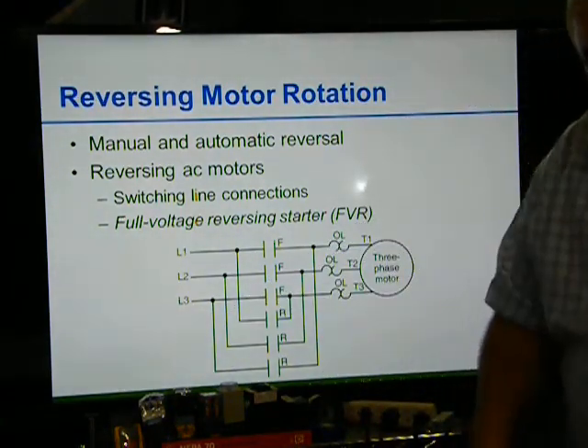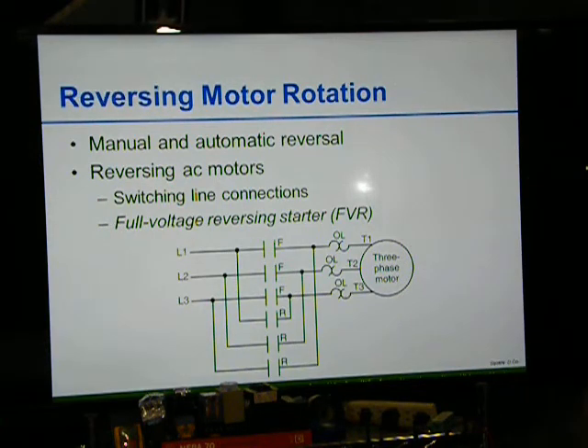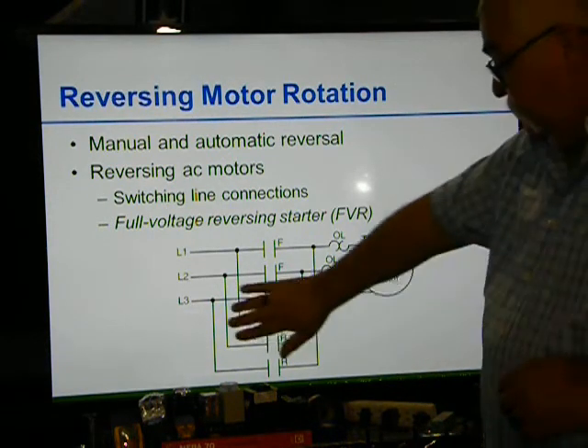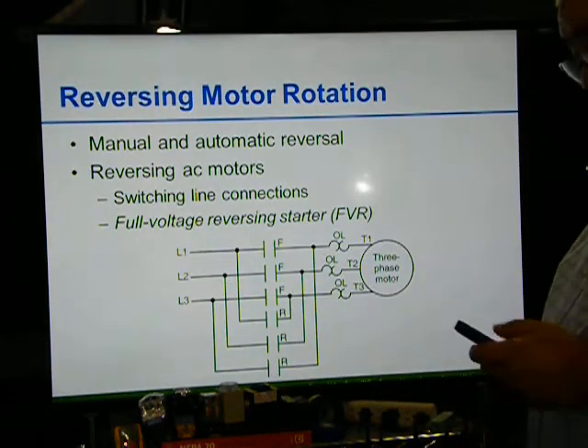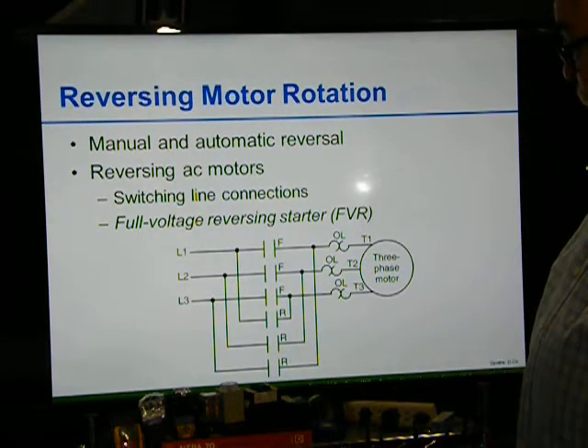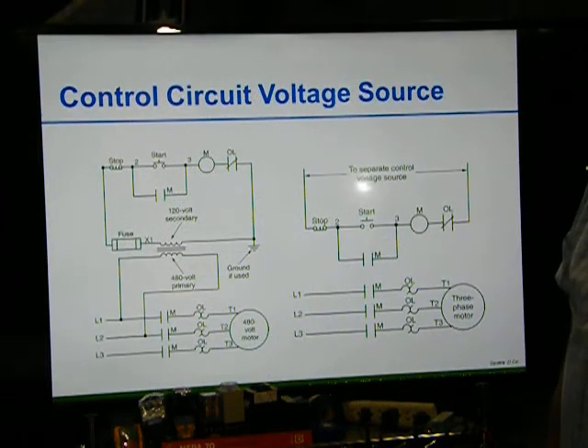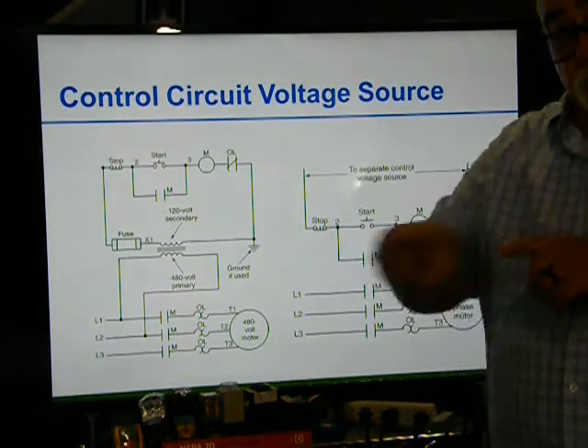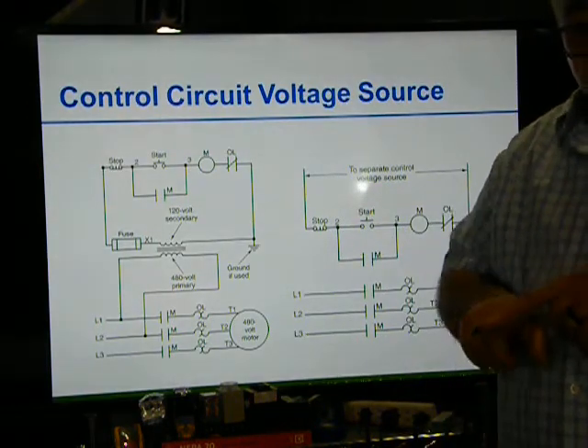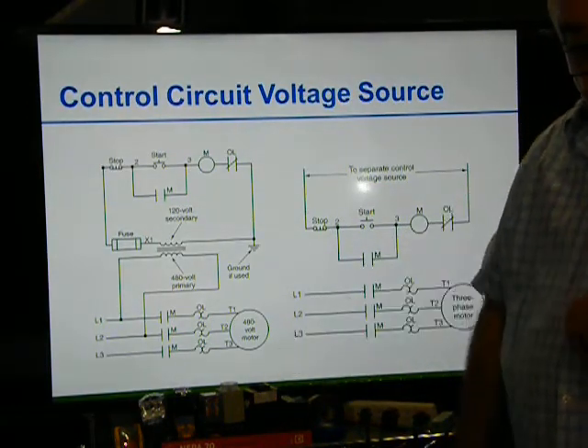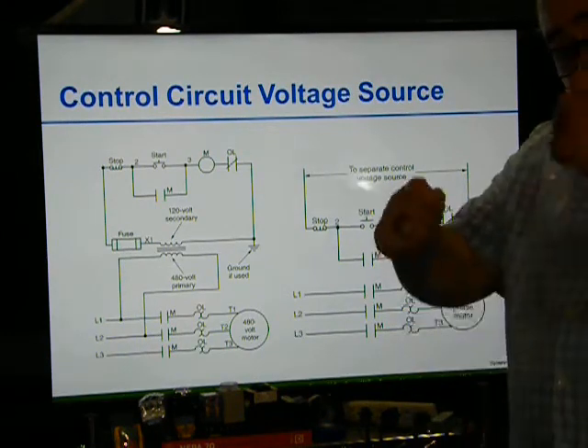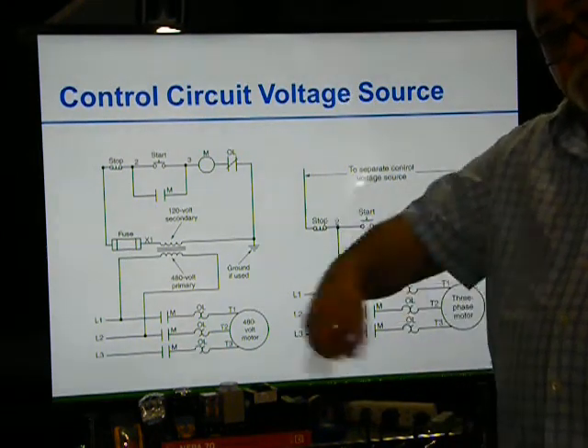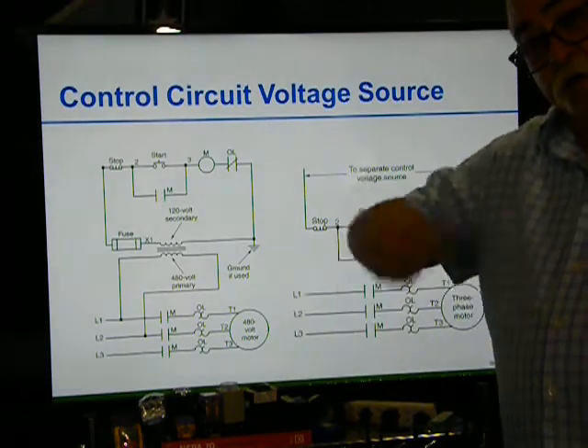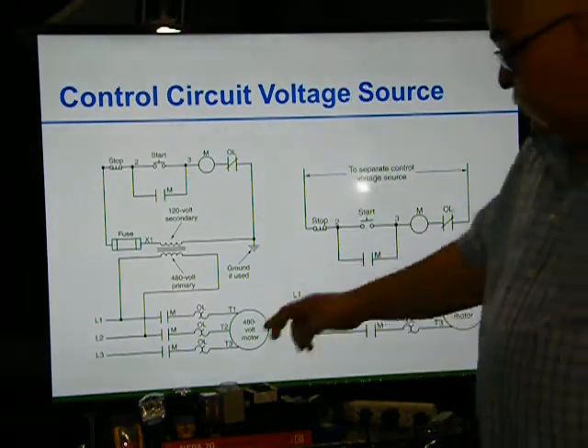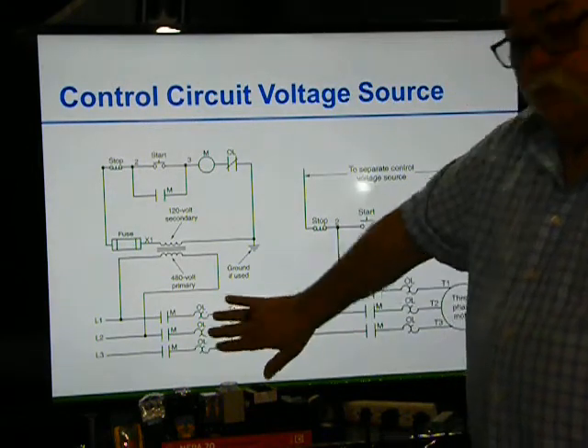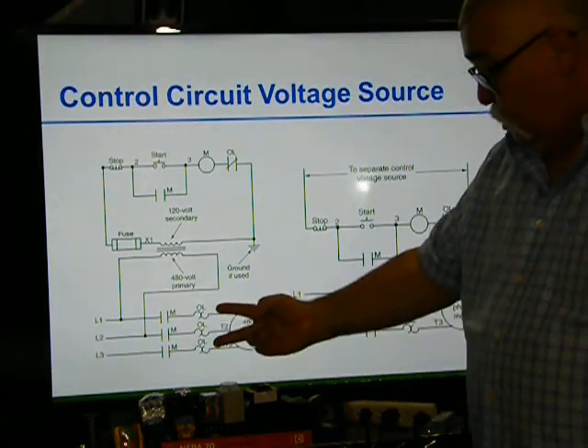Now it starts to run in reverse. Every once in a while you'll put motors in, not noticing that it's reversed. So let's say you've got a motor, and the direction of your motor is that way. The direction the motor needs to run is that way. You power it up, you hook it up, and all of a sudden the motor's turning this way instead of turning that way. What do you do? You come over here and you just get two of these wires and switch them. All you have to do is get two wires and switch them.